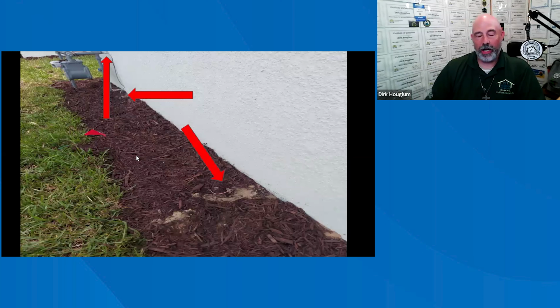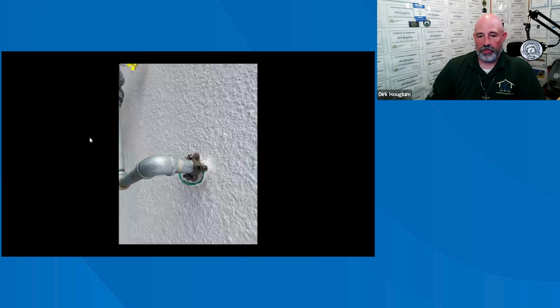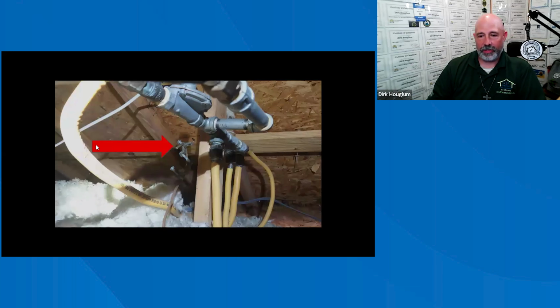So I was doing this one house, brand new house. Matter of fact, it was a whole complex here, and this is a gas meter, and you can see that it's grounded to two spots. Well, according to the NFPA, the National Fire Protection Association, they actually say that it has to be bonded into the electrical system within 75 feet, I believe it is. And here's what the clamp looks like, but it actually has to be bonded.